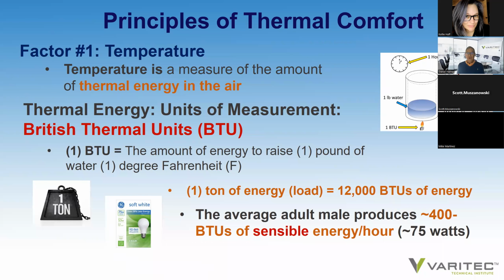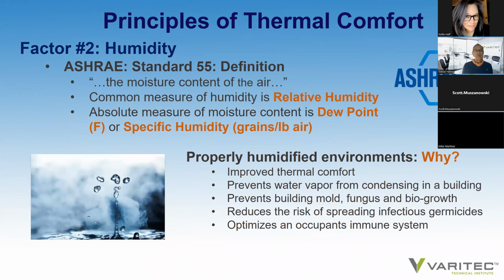The average adult male produces 400 BTUs of sensible energy per hour, somewhat equivalent to a 75 watt bulb. In fact, test labs for HVAC systems often simulate occupants by using towers with 75 watt bulbs mounted in them to generate that sensible heat energy. Another factor that impacts thermal comfort, according to ASHRAE Standard 55, is humidity. Standard 55 defines humidity as the moisture content of the air. A common measure of humidity is relative humidity. Standard 55 and Standard 62.1 have used historically relative humidity as the reference value for moisture content in the air.